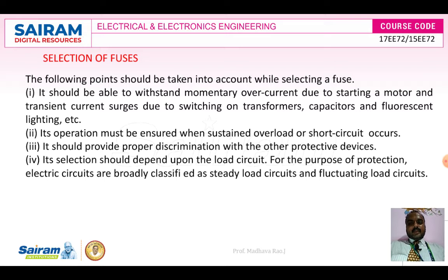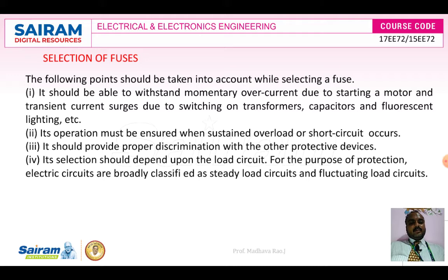The first point is that the fuse should be able to withstand momentary overcurrent due to starting of a motor. So first, based on the motor rating, we are selecting the fuse — to withstand the overcurrent until the starting point is complete.